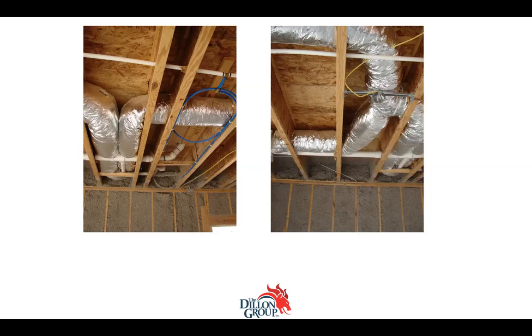You know, this is just horrible. You can't do flex duct like this. You can't bend it 90 degrees and then have it punch through an I-joist where the insulation gets compressed and expect it to do anything. That's just bad. And then on the other side, you've got one duct coming in and it's a certain size and it connects to a T fitting. Well, it turns a 90 degree elbow, and not even an elbow. They just bent it and poked it through an I-joist to connect to a T that wasn't really a T. They fabricated it on site by cutting a hole in the duct and shoving one in there and then taping all the insulation up real nice.